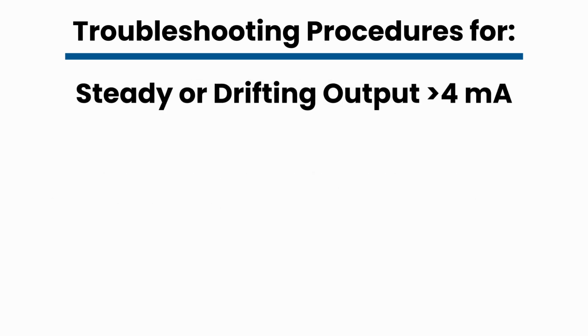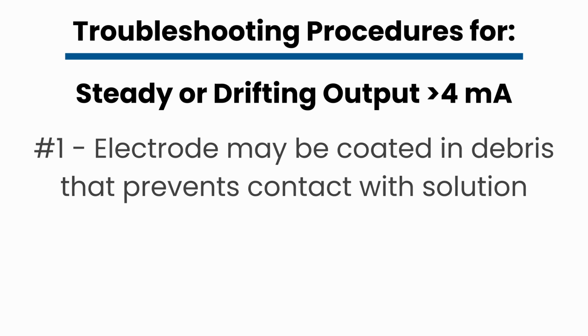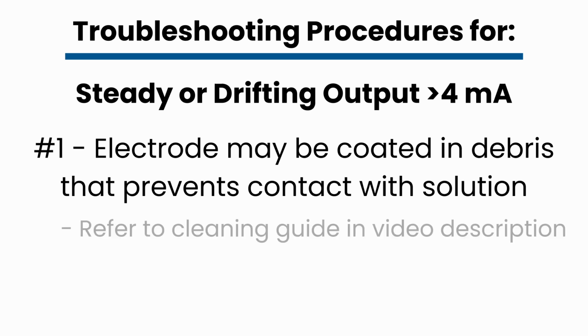If there's a steady or slowly drifting output above 4 mA, then there are two possibilities. Number 1, the electrode may be coated in debris such as fats and oils that prevent contact with the solution. You'll likely know if your application involves debris that would cause this problem. To fix this, refer to the cleaning guides provided in the video description below.